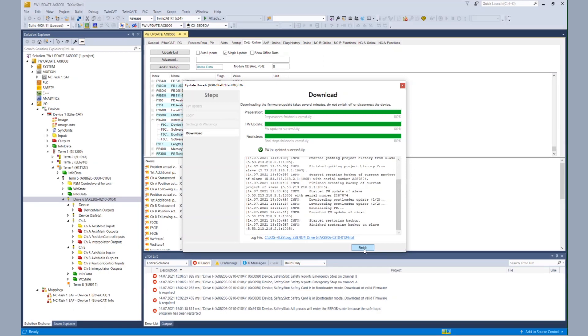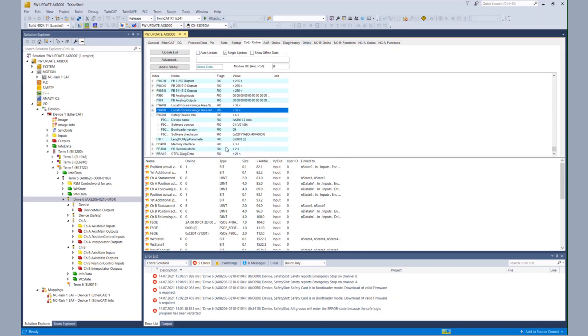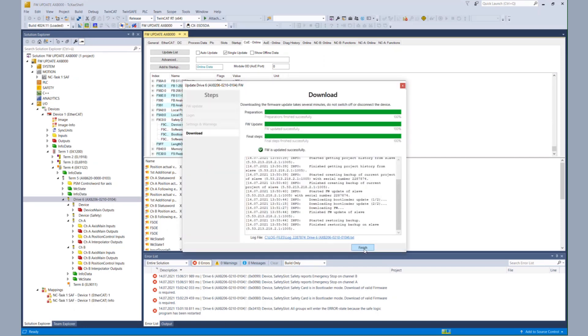After the download, there's only one step to do. We don't have to do it, but we want to do it. We want to check via the COE object if the update was successful. So if we look again at F9C0, we see now that we have a software version 03 and the bootloader version 12. So the firmware update was executed successfully.